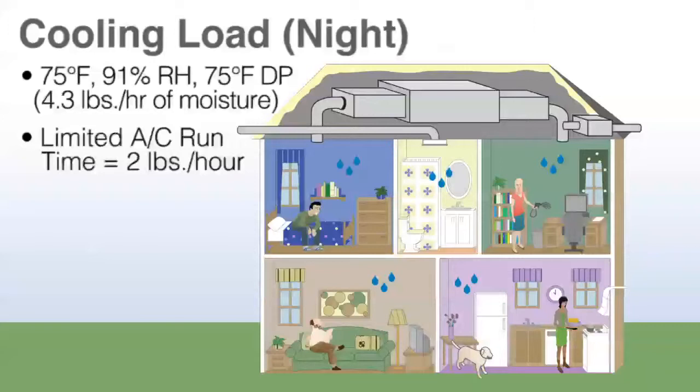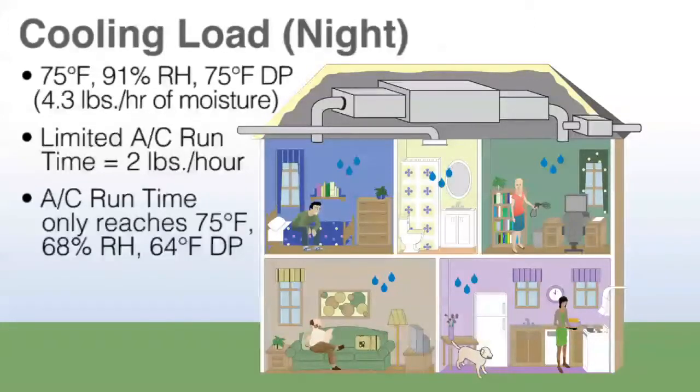Typically the AC is going to run quarter time during the evening, which removes only two pounds per hour. With AC limited run time, we can only reach 75 degrees and 68% RH, which is a 64 degree dew point or 88 grains per pound. So understand that during the day the house was at 50% RH, and as the evening proceeds we lose the humidity control we wanted. Gradually the house will build up to that 68% RH as time goes by.